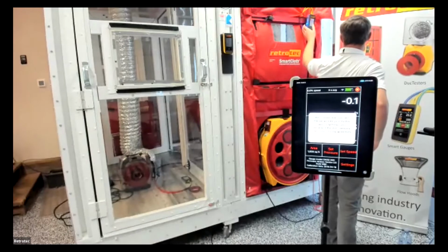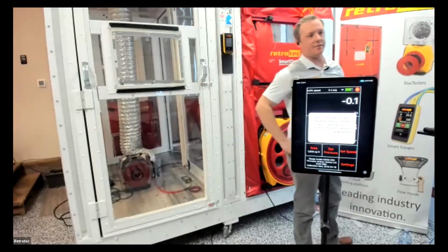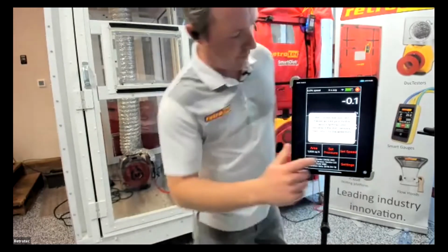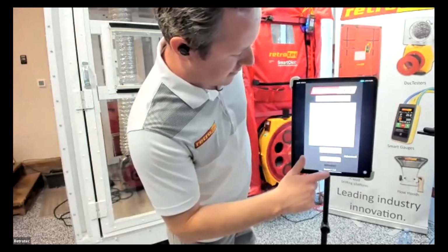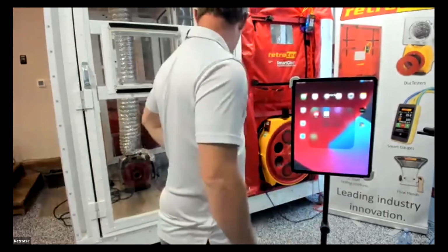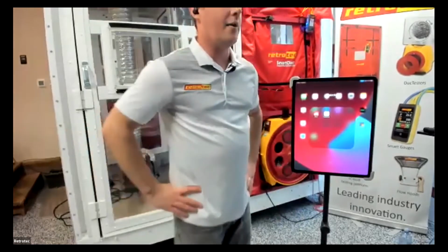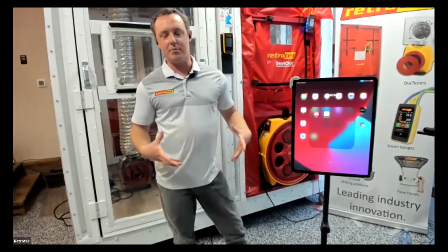Right. So yeah, if it were the other way around, let's see here. Okay, that's right. Cut the gauge off, so it disconnected. Yeah, so if it were the other way around, say I couldn't get to 0, or if I'm doing a total leakage test, if I couldn't get to 25, then that means I'm going to need to open something up. And if I have that fan open and I can't get to 25, something's seriously wrong.